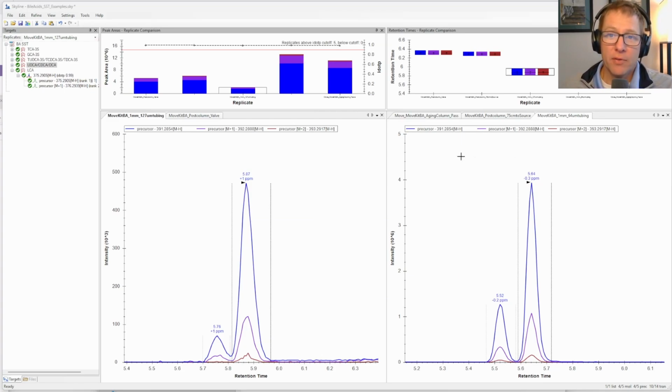And so this example just highlights the importance of only the post-column connection. Really very little else about this separation is expected to be different. And the resolution here undergoes a pretty drastic improvement just from changing that post-column tubing. So remember to use the correct inner diameter, and remember you get double the bang for your buck for inner diameter reduction as opposed to length. Length increases broadening linearly, whereas decreasing the internal diameter decreases broadening squared.